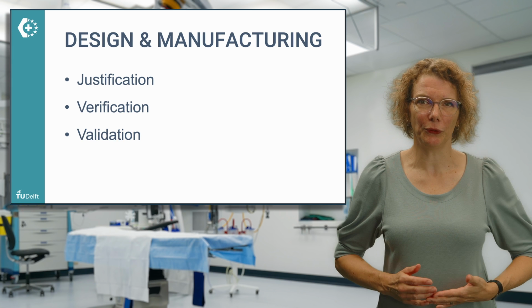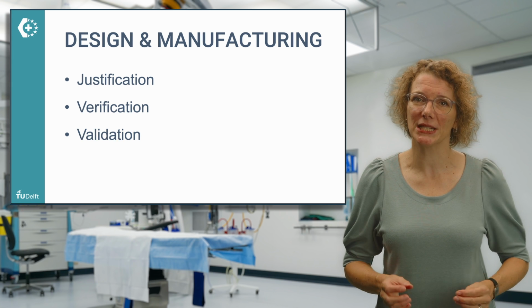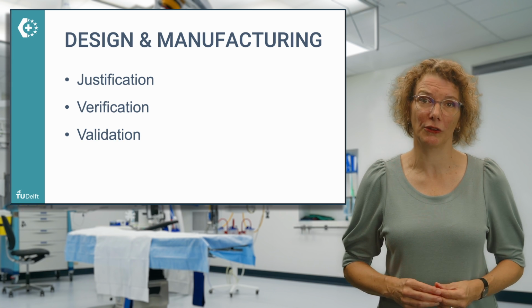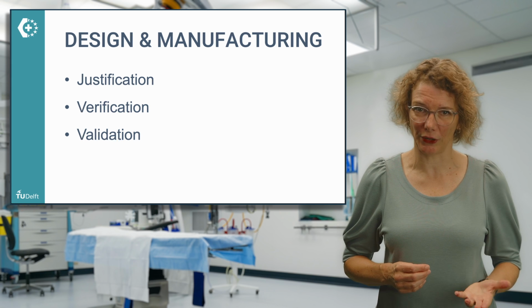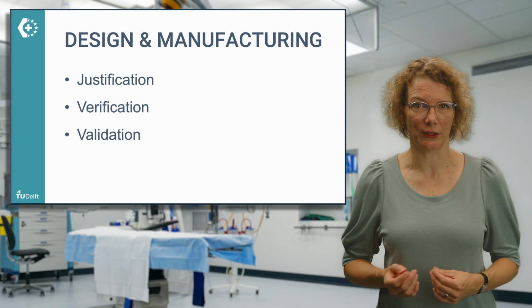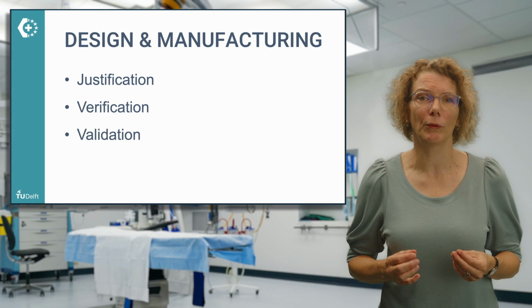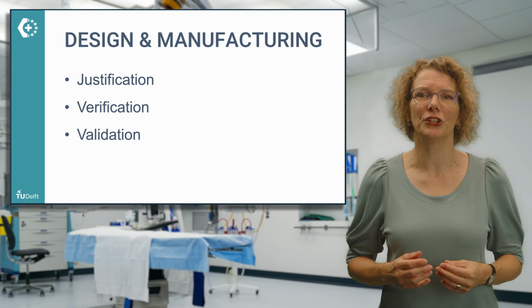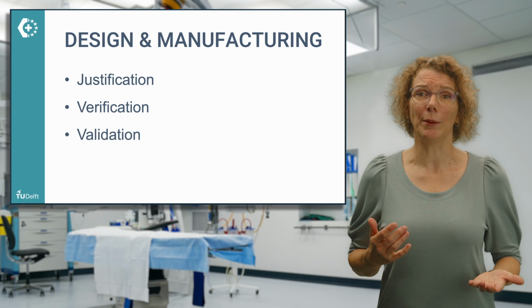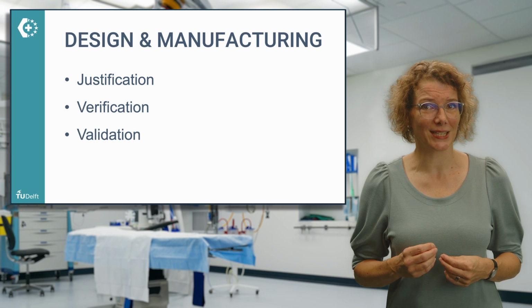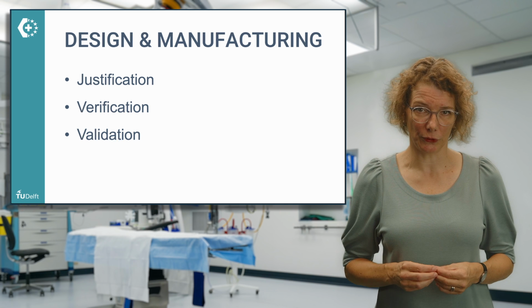Verification means: did you develop the device right? Is it meeting the requirements established at the start of the design process, the MDR's general safety and performance requirements, and the standards you used? Validation: does the device deliver what was intended? Is it achieving the clinical benefits which it aimed to achieve? And is the device adequately meeting the needs of the users?